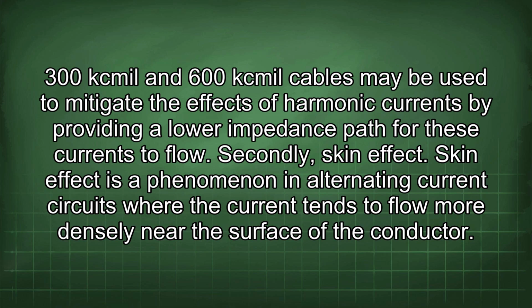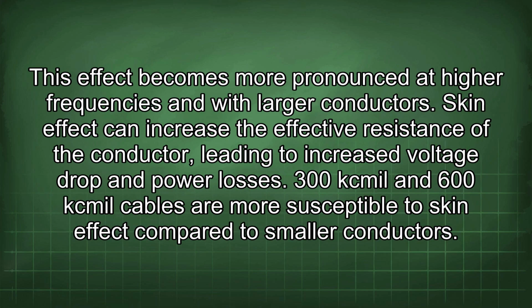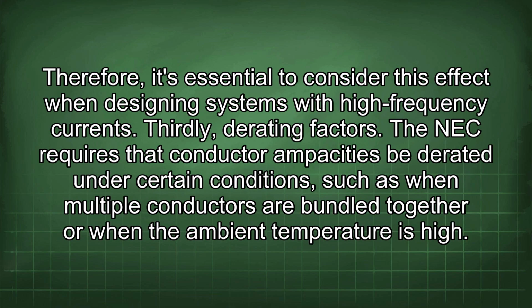Secondly, skin effect. Skin effect is a phenomenon in alternating current circuits where the current tends to flow more densely near the surface of the conductor. This effect becomes more pronounced at higher frequencies and with larger conductors. Skin effect can increase the effective resistance of the conductor, leading to increased voltage drop and power losses. 300kcmil and 600kcmil cables are more susceptible to skin effect compared to smaller conductors. Therefore, it's essential to consider this effect when designing systems with high-frequency currents.